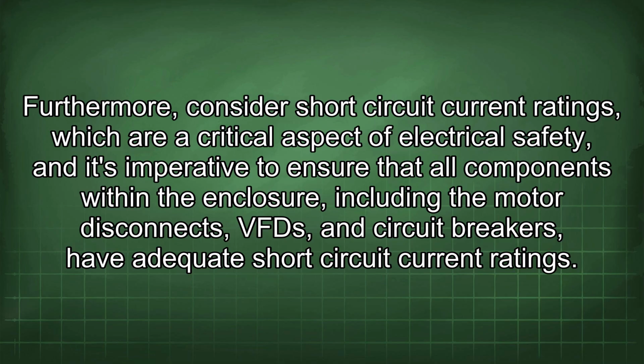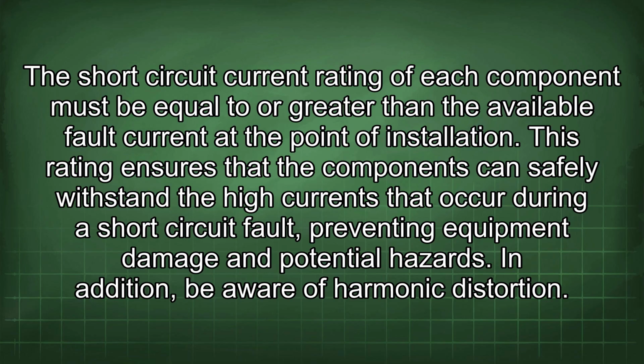Furthermore, consider short-circuit current ratings, which are a critical aspect of electrical safety, and it's imperative to ensure that all components within the enclosure, including the motor disconnects, VFDs, and circuit breakers, have adequate short-circuit current ratings. The short-circuit current rating of each component must be equal to or greater than the available fault current at the point of installation. This rating ensures that the components can safely withstand the high currents that occur during a short-circuit fault, preventing equipment damage and potential hazards.